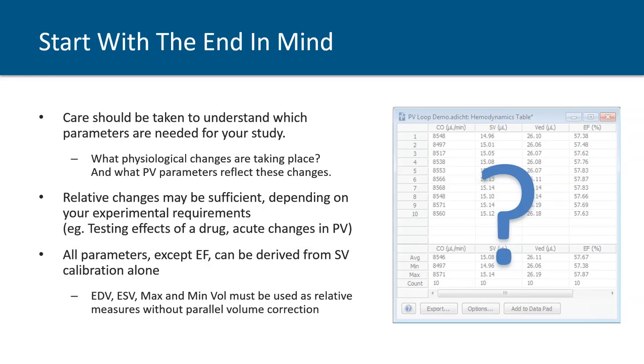You may not need to calibrate at all, and just expressing relative changes within that given study may be sufficient. It's also important to realize that of the two parameters that we indicated before, calibration techniques of hypertonic saline and stroke volume calibration, virtually all parameters from the pressure volume analysis can be derived simply from the stroke volume calibration, without applying the hypertonic saline for absolute volume. If you want ejection fraction, then you would need to apply the hypertonic saline in addition to the stroke volume measurement.